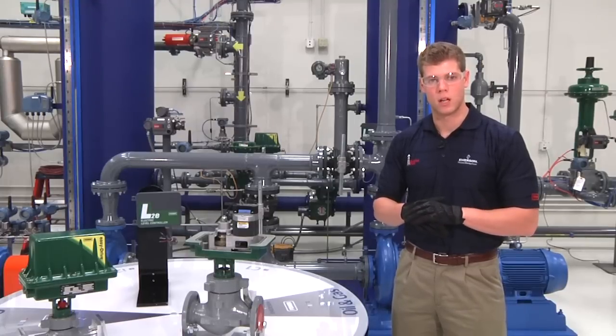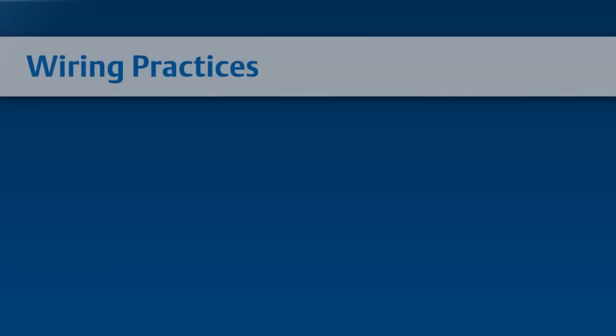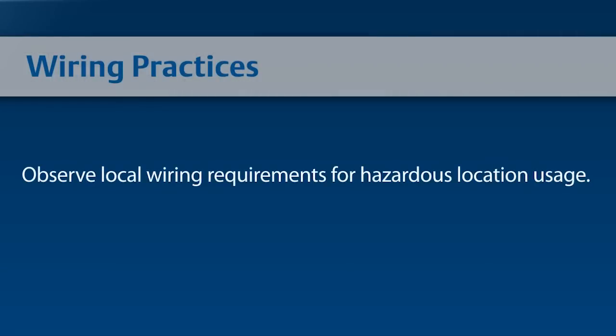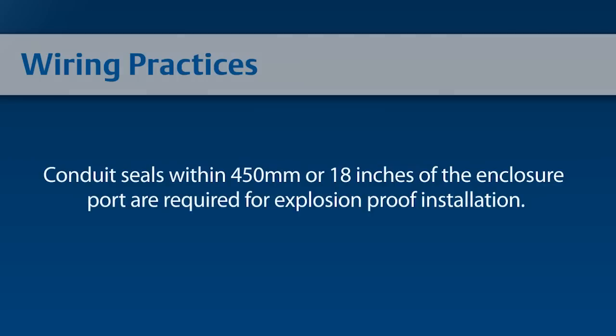Some other wiring practices to follow include: observe local wiring requirements for hazardous location usage. Conduit seals within 450 millimeters or 18 inches of the enclosure port are required for explosion proof installation.